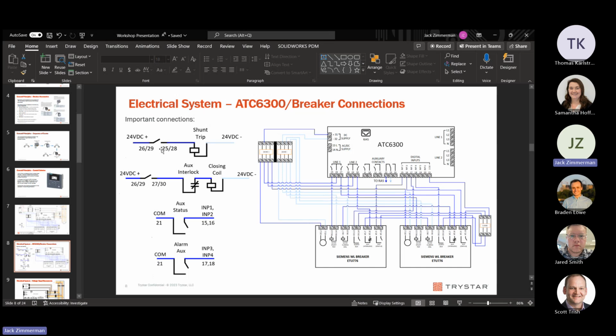And the closing coil is a little more involved. I decided to add what's called an auxiliary interlock to the logic here because we have a mechanical interlock, but I also wanted the software or the electrical system to have an implicit interlock in it. What this does is we have 24 volt DC that also goes through a relay on the controller, so it can decide to activate it or not. But in this case, it has to go through a contact on the opposite breaker first. This contact says, breaker 1, are you closed or open? If breaker 1 is closed, this auxiliary interlock is going to be open, so it will not let the controller close breaker 2, because we can't have both breakers closed at the same time. It's a really bad deal.